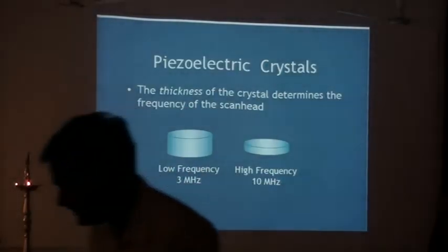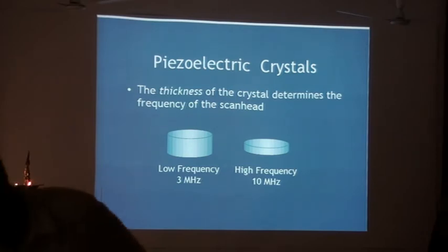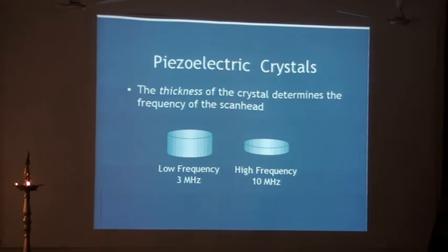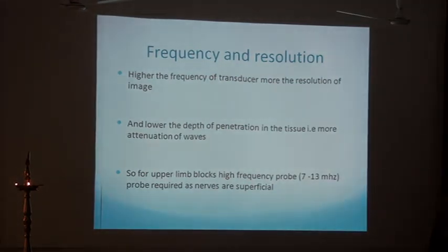The piezoelectric crystals present in the transducer head determine the frequency of this probe. The thicker the crystals, the lower the frequency, and the thinner the crystals, the higher the frequency of the probe. The frequency affects the resolution of the image. The higher the frequency of the probe, the more the resolution of the image. But at the same time, the depth of penetration of the ultrasound wave decreases with higher frequency, because there is more attenuation of the ultrasound wave.